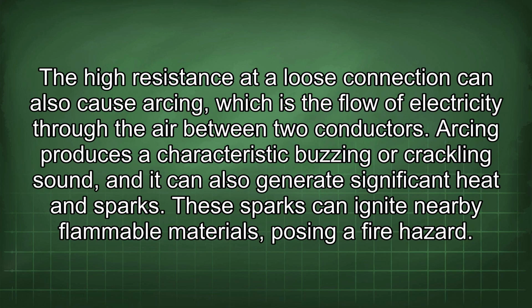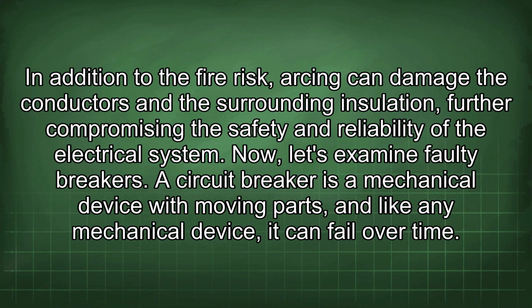The high resistance at a loose connection can also cause arcing, which is the flow of electricity through the air between two conductors. Arcing produces a characteristic buzzing or crackling sound, and it can also generate significant heat and sparks. These sparks can ignite nearby flammable materials, posing a fire hazard. In addition to the fire risk, arcing can damage the conductors and the surrounding insulation, further compromising the safety and reliability of the electrical system.